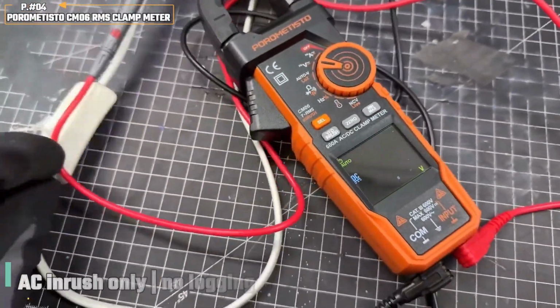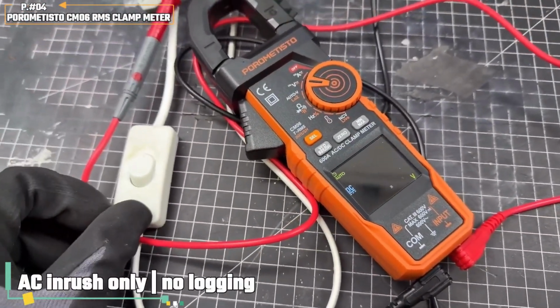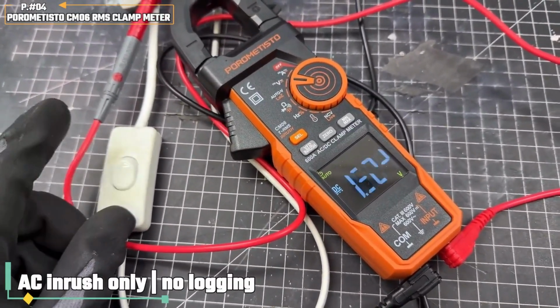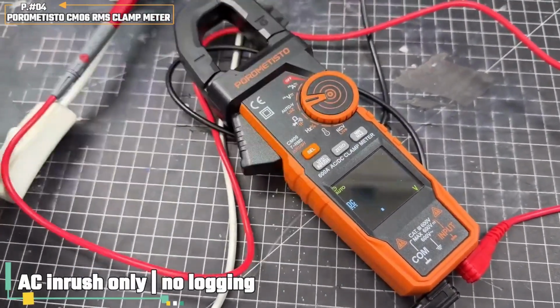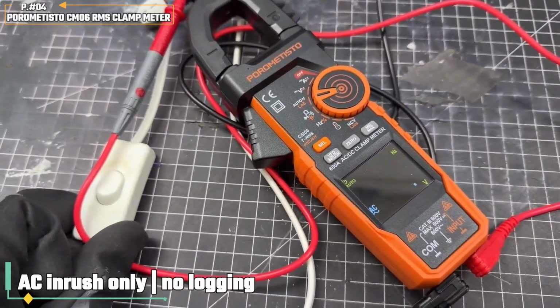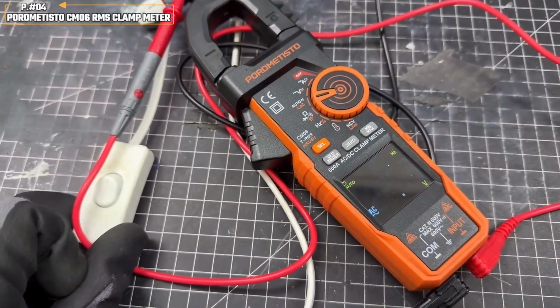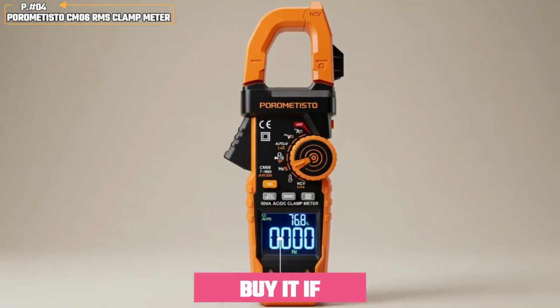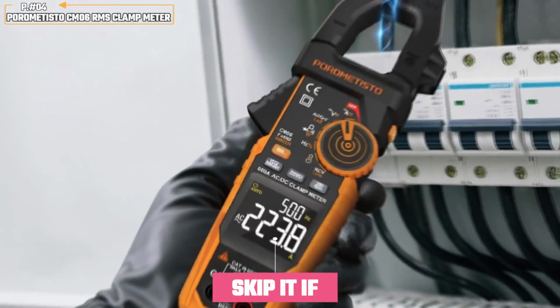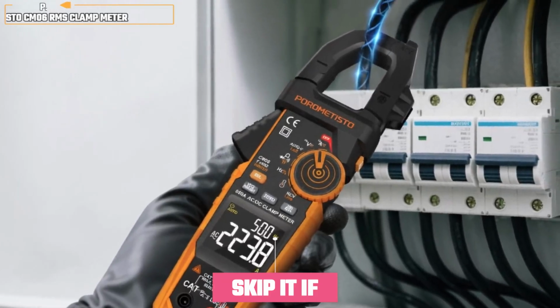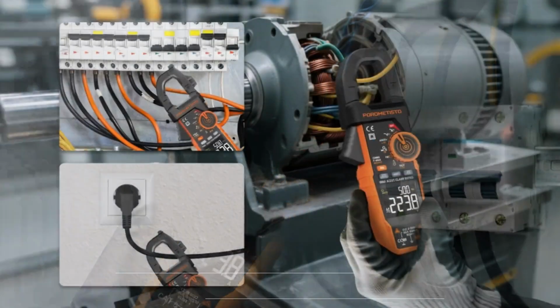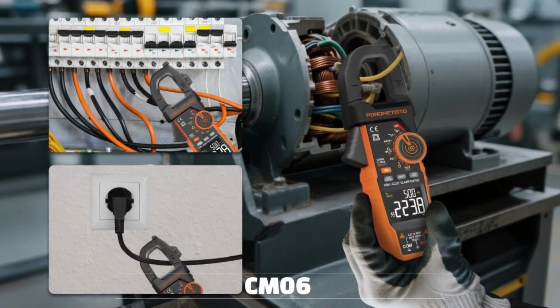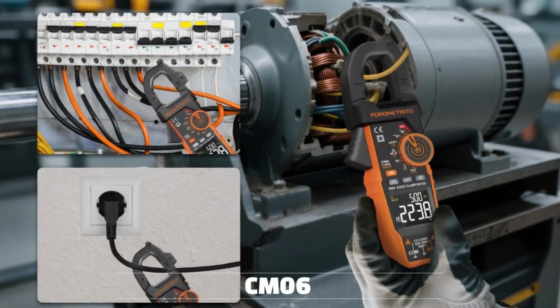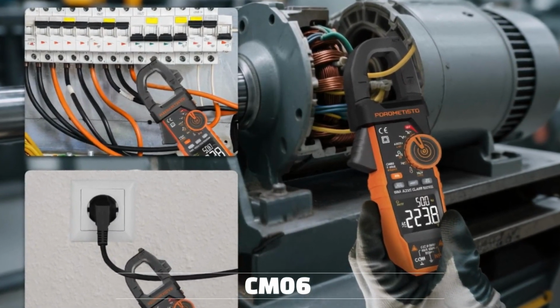Inrush measurement works only with AC current, and this meter does not provide Bluetooth logging or long-term graph recording. Also, make sure you buy the standard 600-amp CM06, not the higher-range CM06 Pro. Buy it if you troubleshoot motors, compressors, VFD systems, or ghost voltage readings. Skip it if you mainly need simple household measurements or professional data logging. The CM06 earns 4th place by combining inrush capture, VFD filtering, and LOZ testing at an accessible level.